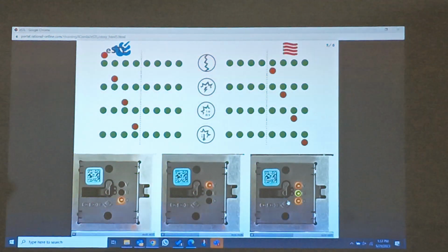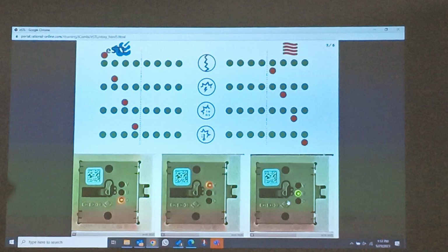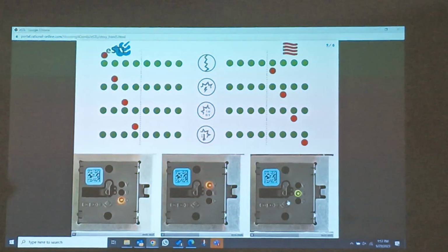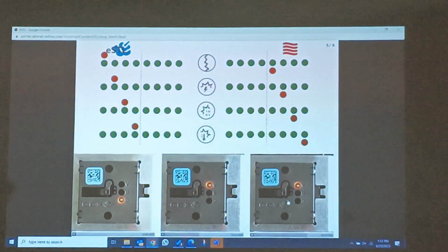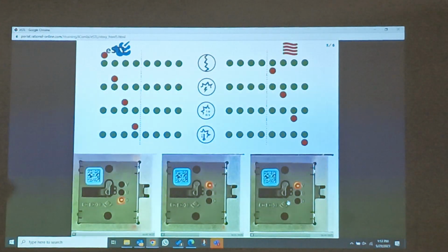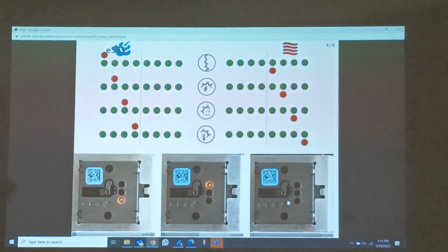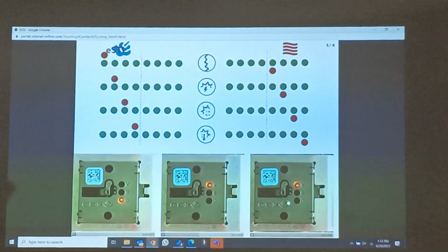Hot air temperature sensor is not showing temperature. The sensor is disconnected, meaning the connection is open. So there is no connection between the sensor and the EST.